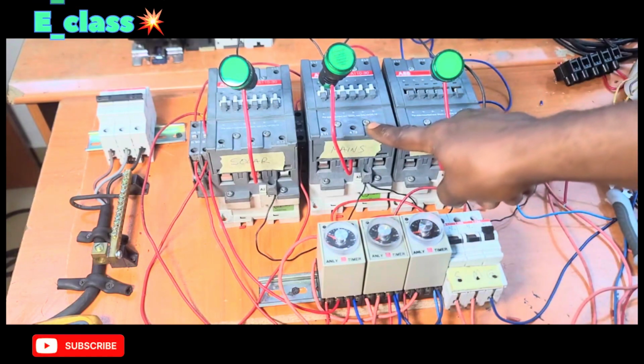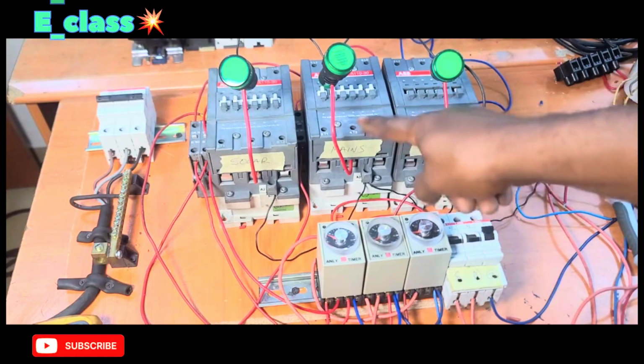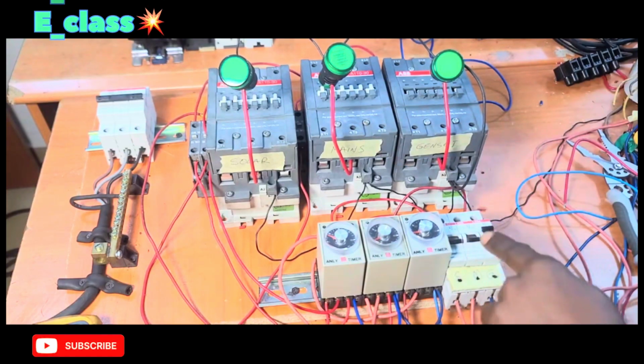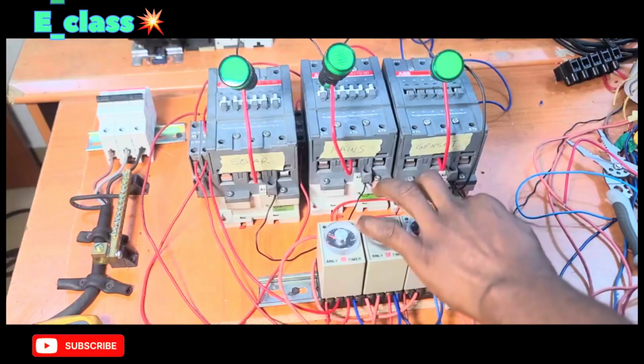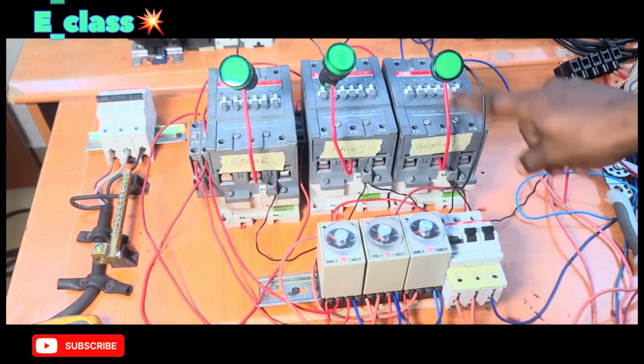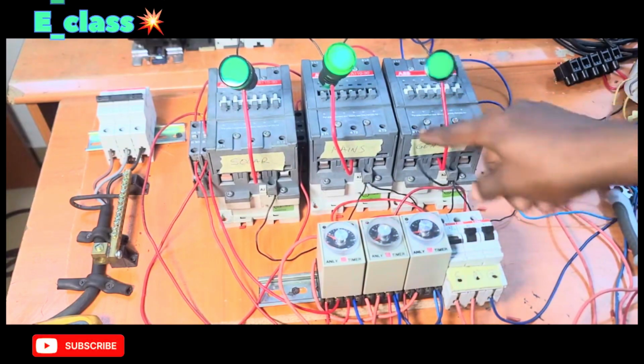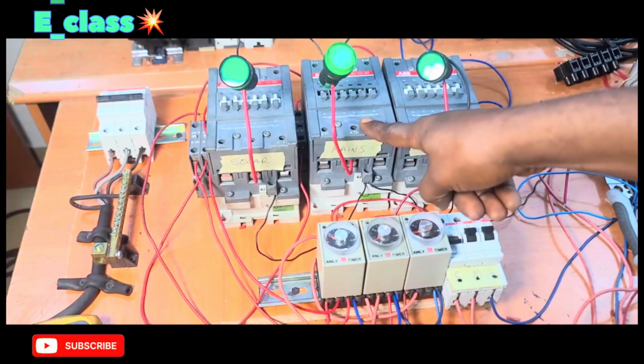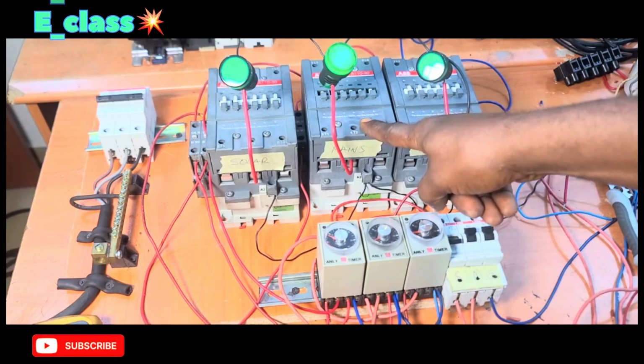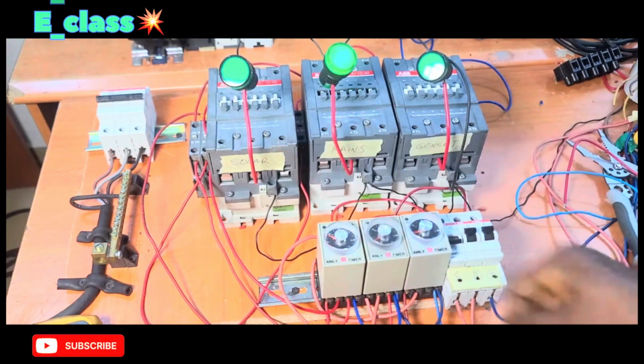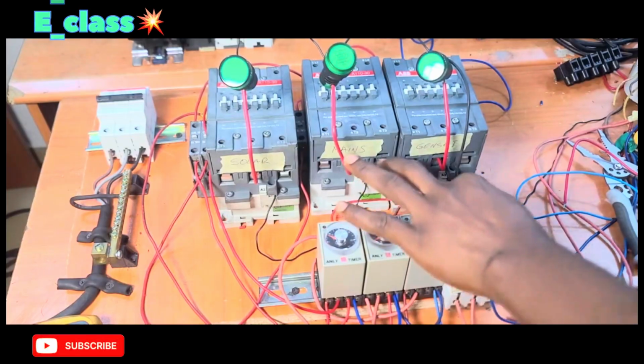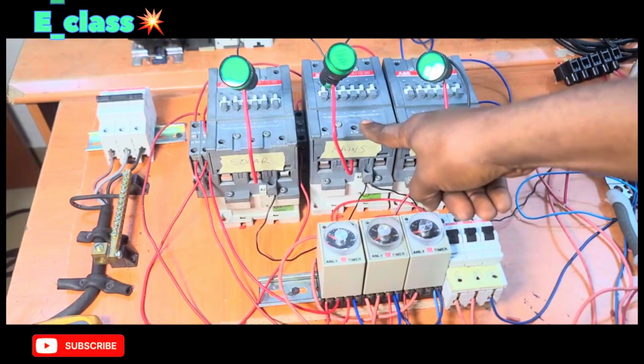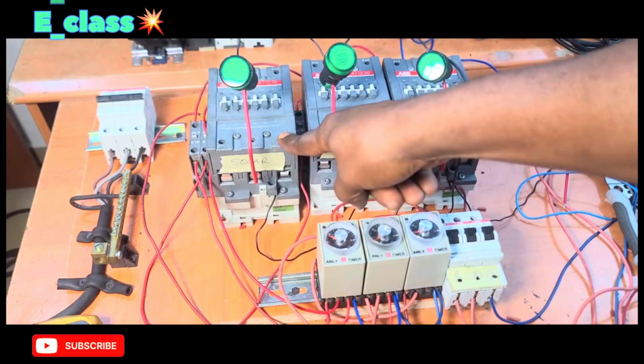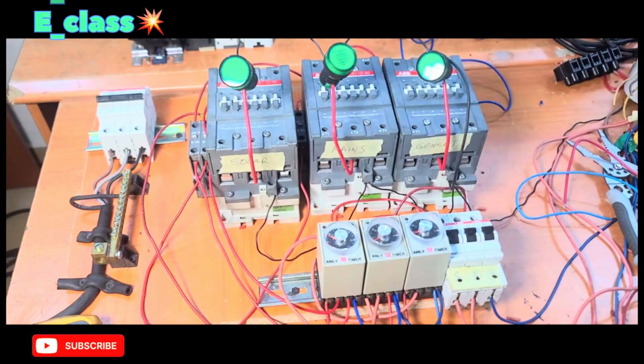And when this one is restored, we put this one on. It cuts off this one immediately, and then after the delay, it connects this one. All right? And when this one is on, this way, it cuts off this one immediately and delays for some seconds and connects this one.